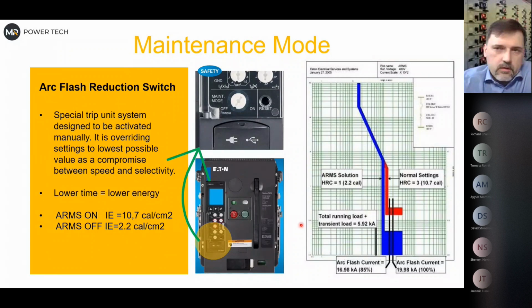It works very simply. There is a switch inside the trip unit. We can activate it or deactivate it. It's supposed to have a lockout tagout feature also, as a cover here, so no one can change it. It works in the way that for the time we are in the substation doing something on live equipment, it will bypass the settings to the minimum level. We always have to check it because it doesn't always work.